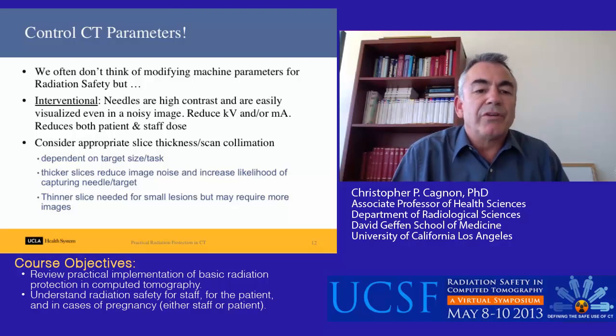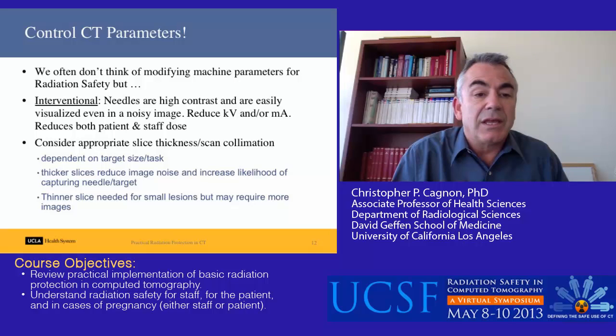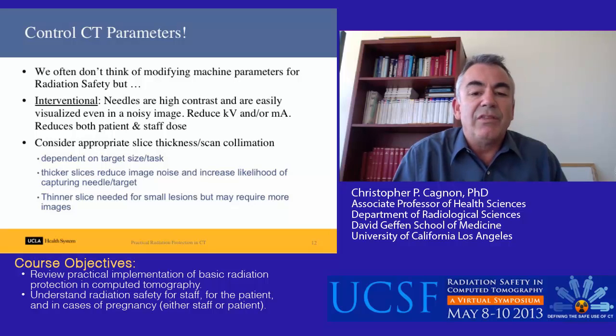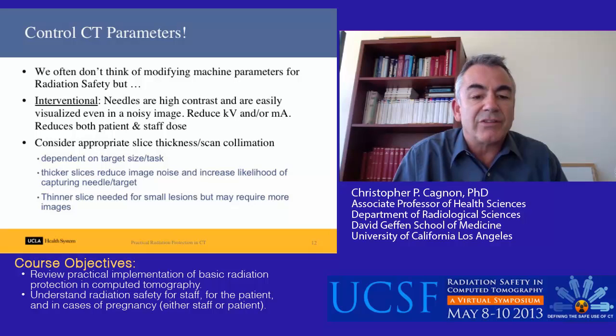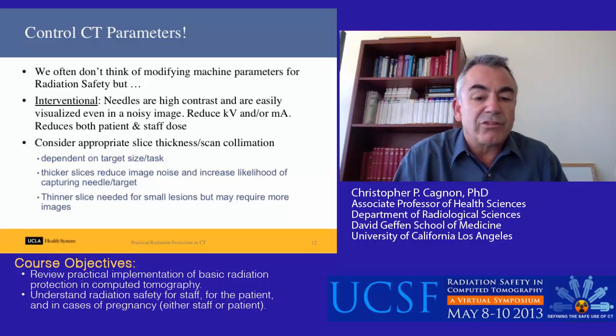We often don't think about modifying machine parameters for radiation safety for the staff. Keep in mind that for interventional procedures, if you're using needles — which are very high contrast objects easily visualized even in a noisy image — this allows you to reduce the kV and/or the mA, reducing both patient and staff dose. You should also consider appropriate slice thickness and scan collimation for your imaging task, dependent on the target size. Thicker slices reduce image noise, allowing less mAs and increasing likelihood of capturing the needle and target, but you may need thinner slices for small lesions.